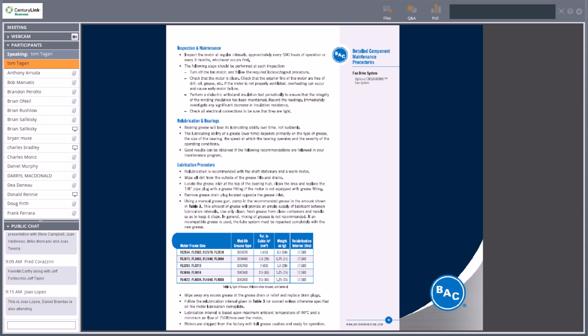So there's different areas. There's the motors and the bearings to grease. Most manufacturers offer an extended lubrication line so that you can re-grease the bearings from outside of the cooling tower, so that you're not crawling in or trying to work off a ladder or a platform inside of the tower. So again, just pointing out that having these O&M on hand is a very important piece of your toolbox, if you will.